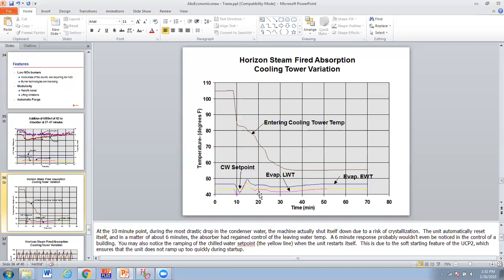and they're saying about 6 minutes before we got control of it. You may also notice the ramping of the chill water set point, the yellow line. I'm sorry, let's see. Yeah, the yellow is the set point. So this was the actual evaporator temperature here. Okay. So the yellow shows that it actually changed the set point when it restarted itself. It got itself back in proper operation. This is due to the soft starting feature of the controls, which ensures the unit will not ramp up too quickly during startup.